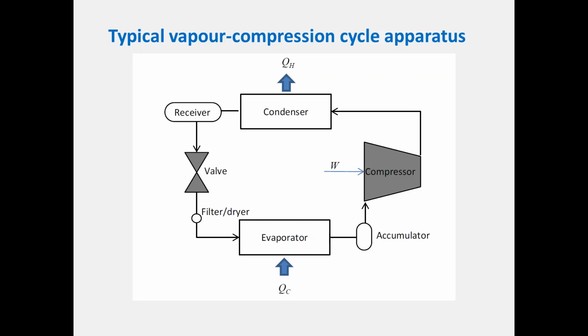So let's look at a diagram of a typical vapor compression cycle apparatus. The four essential components, of course, are the compressor, the condenser, the expansion device or a valve, or it might just be a restriction in the line, and the evaporator. Now, most cycles will also have various other components. Most will have some sort of filter or dryer to protect the compressor. Normally there will be a receiver, or basically a refrigerant store for excess refrigerant in the cycle. And then what I call the accumulator, some people also call that a receiver. That's just another device that protects the compressor from droplets entering into it. So if there's any liquid coming out of the evaporator, it'll fall down to the bottom of that accumulator and evaporate before it goes into the compressor.